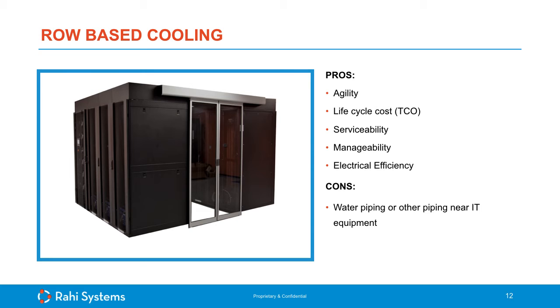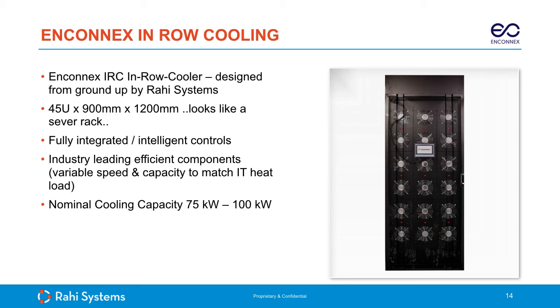Also much easier to design with redundancy, which is key. In a row or a pod level, you can design it around an N+1 or a 2N, where with liquid and rear door cooling you cannot. However, one of the big cons is like liquid and rear door cooling. There can be multiple piping connections above or below, near the IT equipment, which also is a potential for leaks. So let's talk about the Enconnex IRC and how Enconnex is designing to reduce this risk.